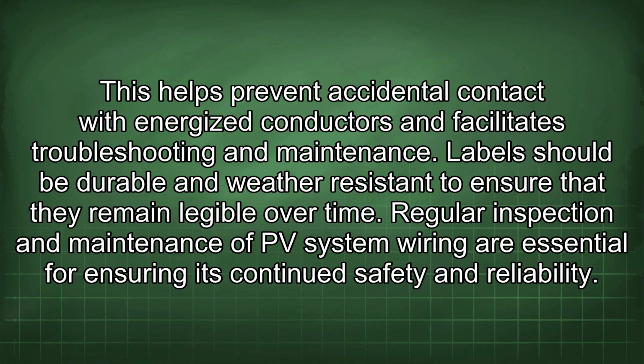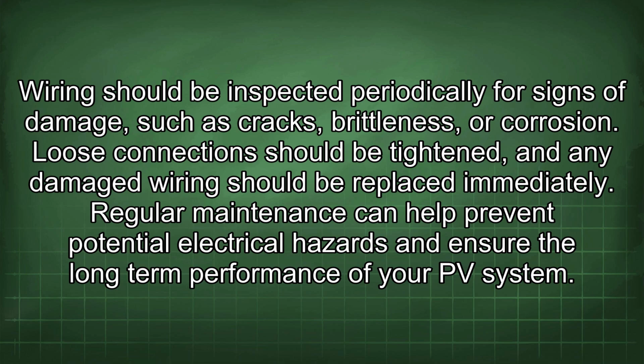Regular inspection and maintenance of PV system wiring are essential for ensuring its continued safety and reliability. Wiring should be inspected periodically for signs of damage, such as cracks, brittleness, or corrosion. Loose connections should be tightened, and any damaged wiring should be replaced immediately. Regular maintenance can help prevent potential electrical hazards and ensure the long-term performance of your PV system.